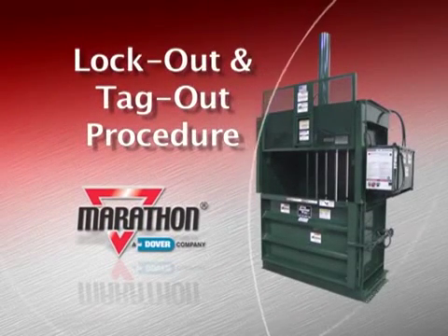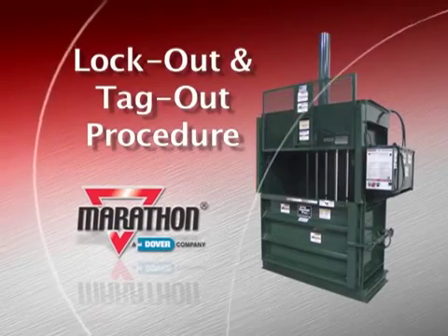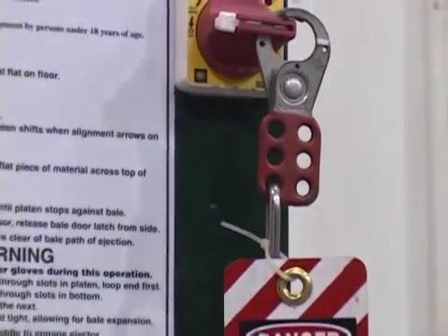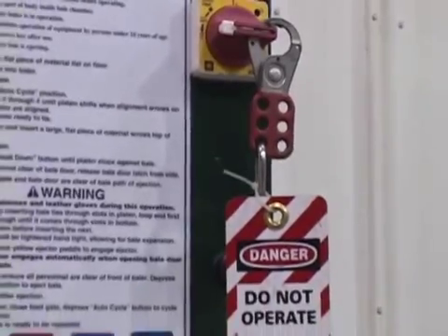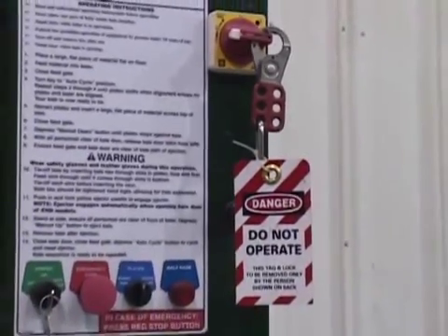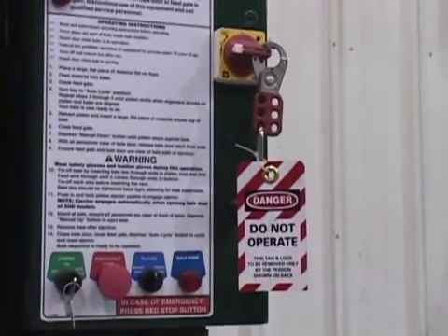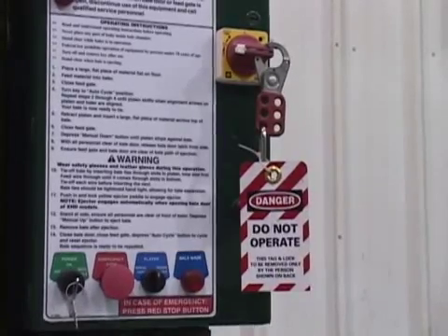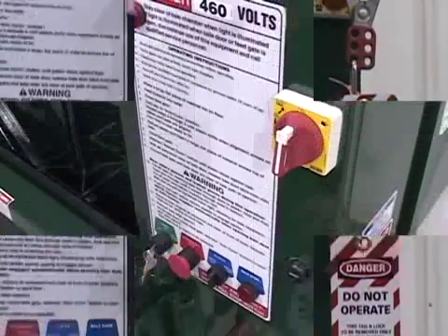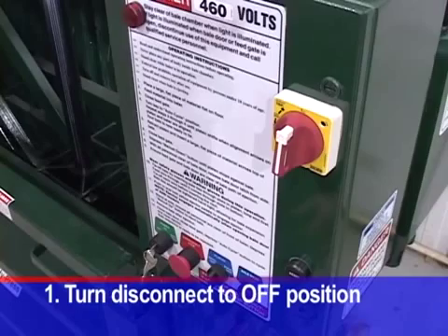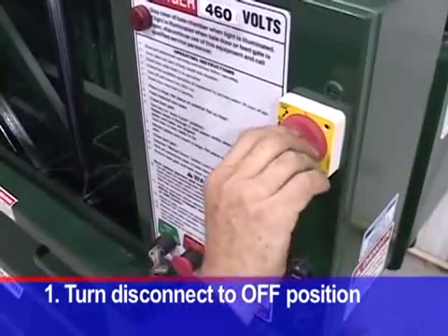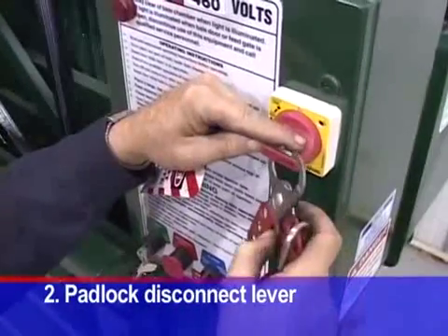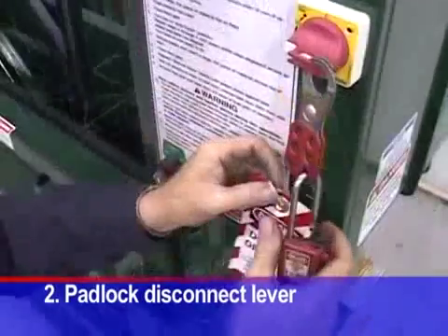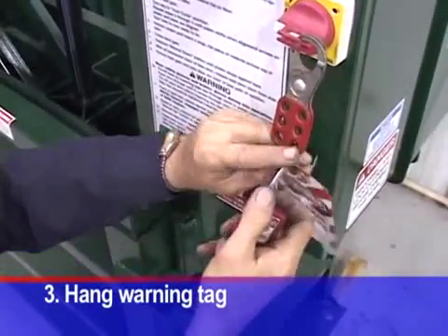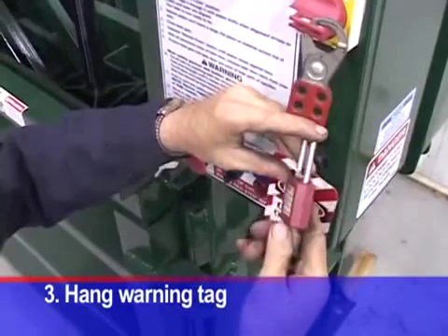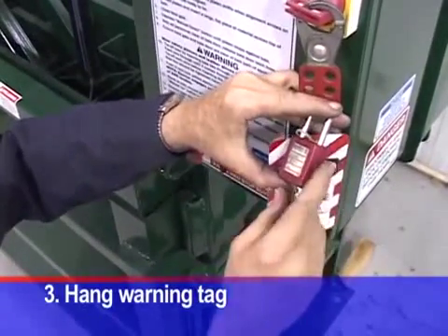The following lockout and tagout instructions are provided as minimum guidelines. Specific lockout and tagout instructions may vary from company to company, such as multiple locks may be required, or other machinery may need to be locked out and tagged out. If your machine is equipped with the optional electrical disconnect, move the disconnect lever to the off position. Lock the disconnect lever with a keyed padlock and take the key with you. Along with the padlock, place an appropriate, highly visible warning tag on the disconnect lever.